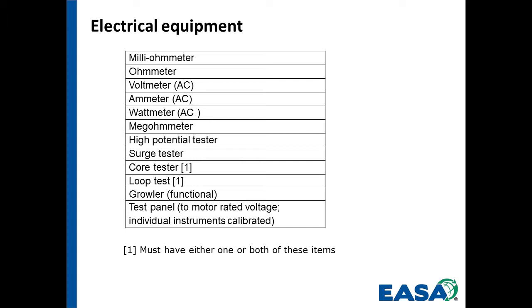Okay. Other things: the megohmmeter, high-pot tester, surge testers. The surge tester was something that was incorporated into the program when AR100 was revised in 2015. Prior to that, it was optional. It wasn't required, and now it is. And in looking back, all of the accredited service centers from the first one on, in fact, did have surge testers, and they were part of the program.